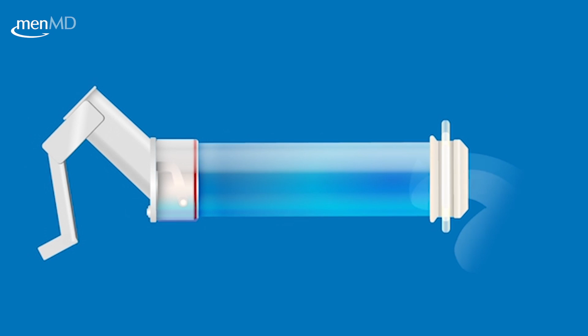To ensure a vacuum will be created, insert only your penis into the penile tube and apply slight pressure to the seal with the transfer sleeve against your body at the base of the penis. It may be necessary to groom the hair at the base of the penis. Make sure the constriction ring on the transfer sleeve is in the correct position, with the handles to the top and bottom.